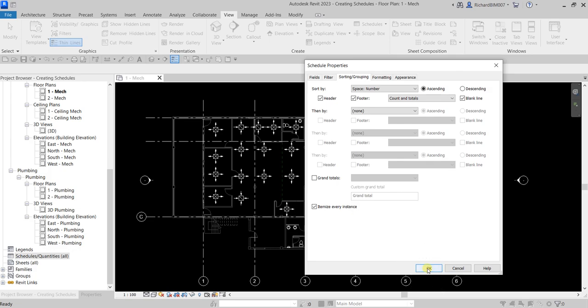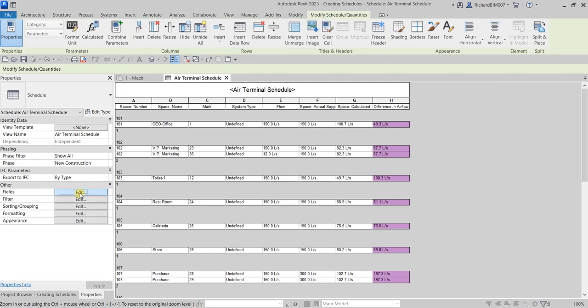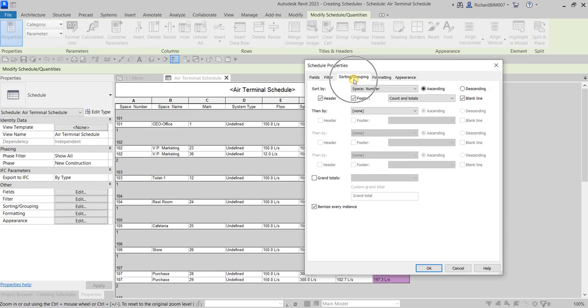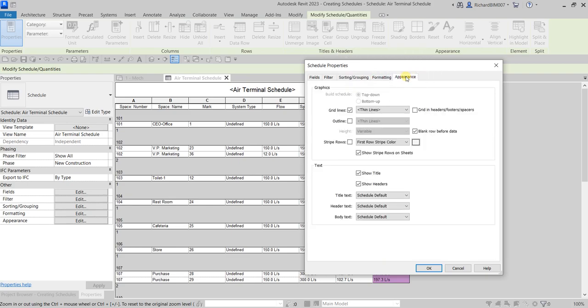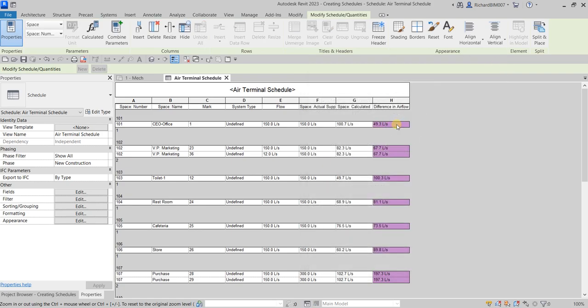The schedule is now sorted by Space Number. If you want to edit it again, just go to Properties and make changes there — you can use the filter, sort, format, or change the appearance. Notice the violet-colored cells in the Difference in Airflow column — these indicate that the actual amount of air being supplied to the room does not meet the design airflow requirements within the range of plus or minus 9.5 liters per second.